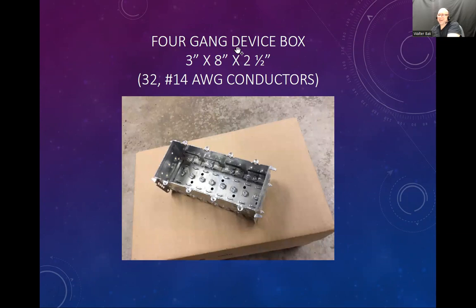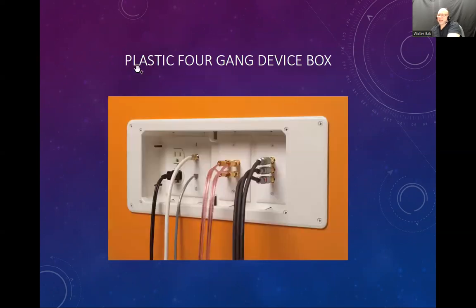4-gang box. Okay, so look, 3 by 8, 2, 4, 6, 8. So that would be 4 single gang boxes in one. All right, so that can fit 32 14-gauge conductors.